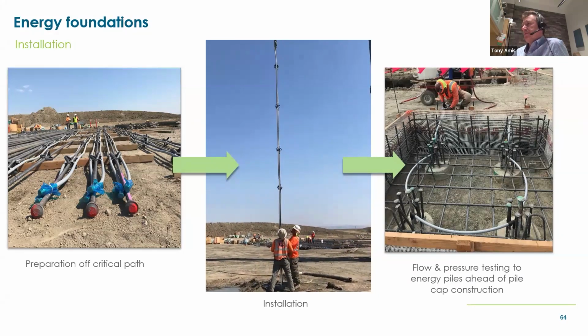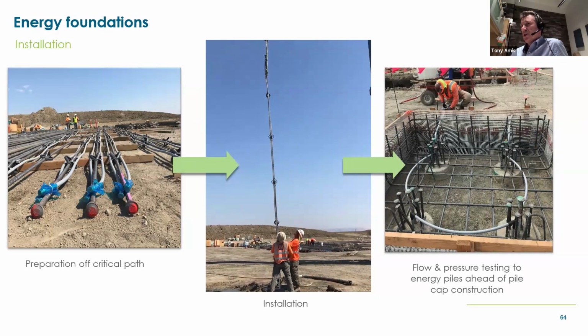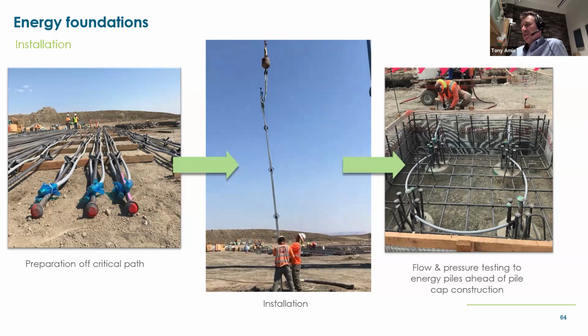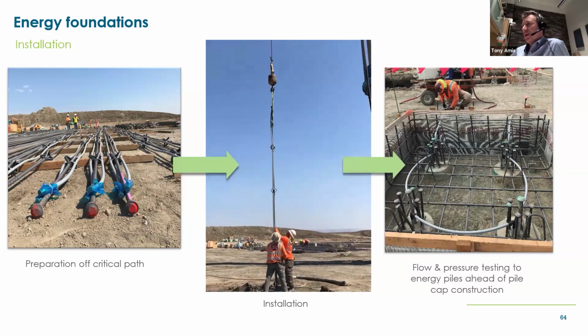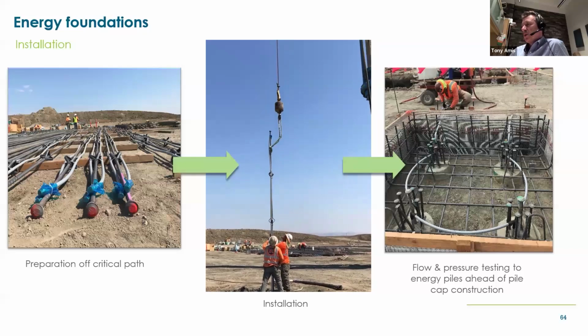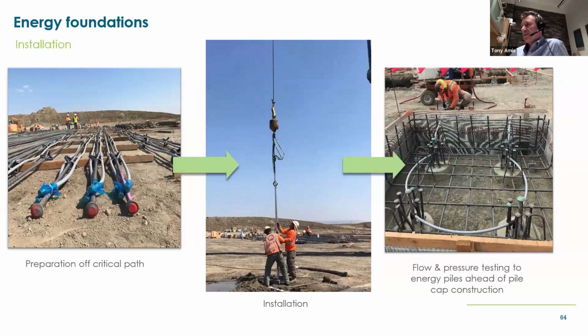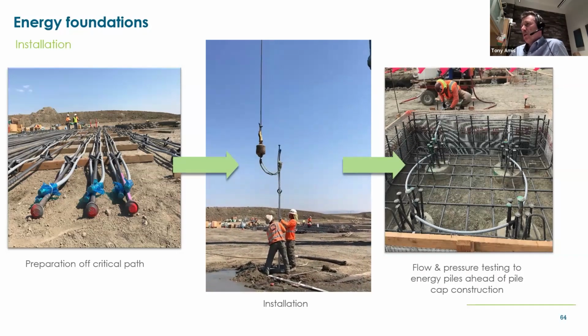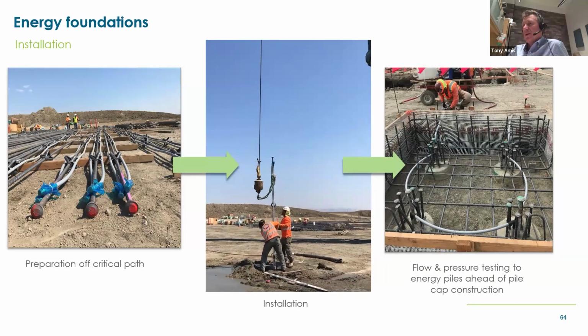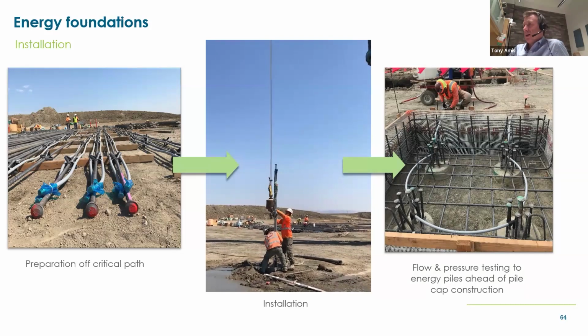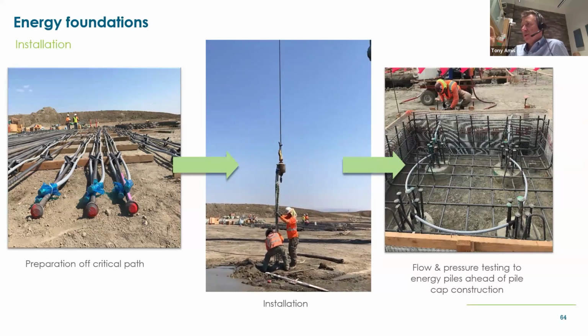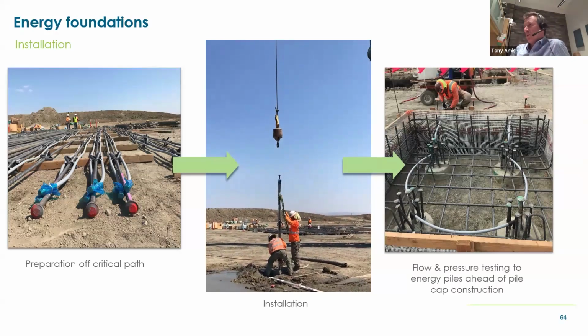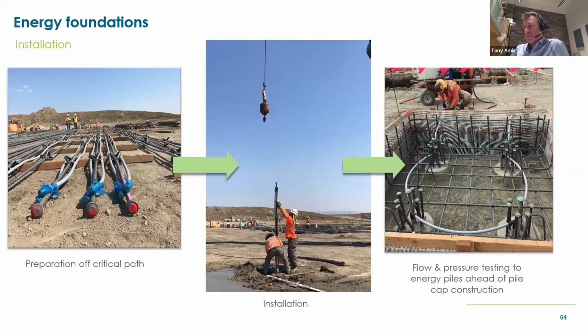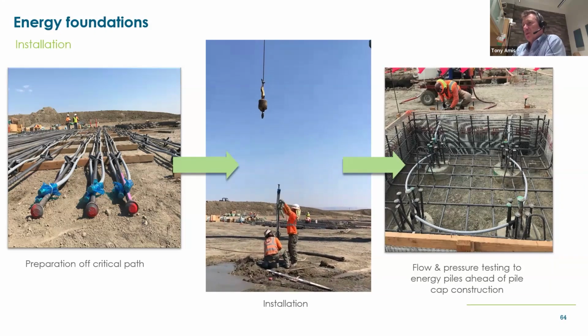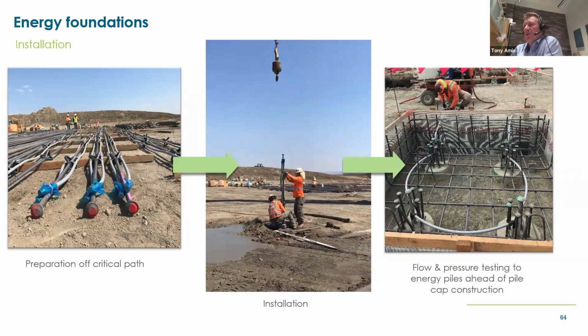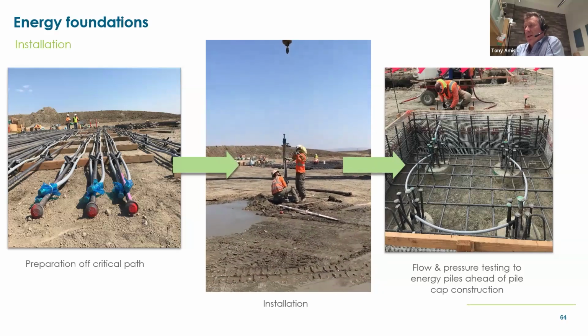So again, you need to take that into account when you design these systems. What we see here is these four piles on the right-hand side, all being connected together, which, when added together, is the equivalent of a single borehole. And that's run back to a sub-manifold location, so if there is an issue later on, they can be isolated. You can see there that was a very quick installation of a geothermal loop in one of the piles.